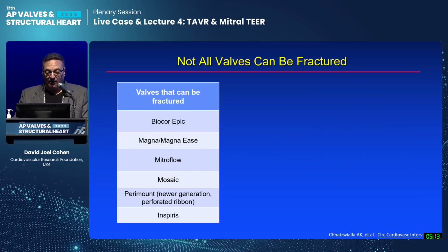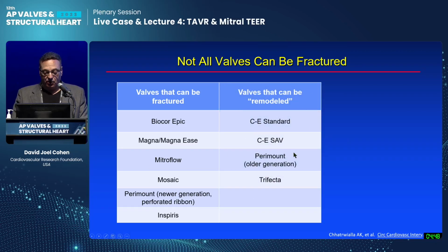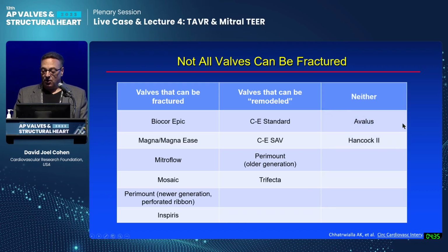If you're thinking about doing valve fracture, you need to know which valves can and can't be fractured. So this is a list of the common valves used in the United States that can be fractured. Very importantly, the Magna and Magna Ease, which are among the most common aortic valves that are used, are fracturable. The Mitroflow also, the Perimount, and now the Inspiris valve, which is a valve made specifically for not even valve fracture, but with an expanding ring. So all of these valves can be fractured or expanded. Then there's a secondary set of valves that includes the Trifecta valve that we were discussing yesterday, where the valves can't be fractured, but they can be remodeled, what we call bioprosthetic valve remodeling, where you expand the posts of the valve. And then finally, there are the valves that can be neither, the Avalus valve and the Hancock II valve. You can't budge these at all and shouldn't bother even trying.